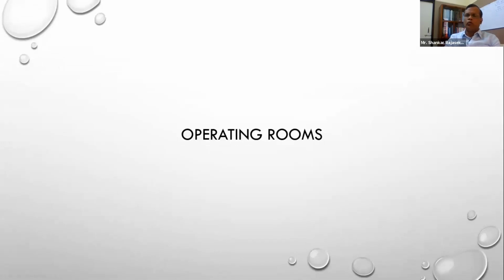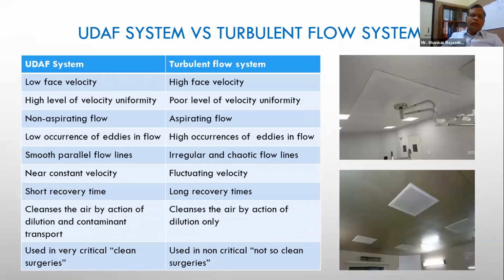So we'll now go to the operating rooms specifically. We very commonly call them laminar flow theaters, modular theaters; we use these words very commonly nowadays. We had the turbulent flow systems earlier, and now most of the hospitals are moving towards what we call unidirectional airflow systems. It's typically not to be called laminar in the true engineering meaning, but a unidirectional flow system. And it is the same one that the HTM calls an ultra clean ventilation system.